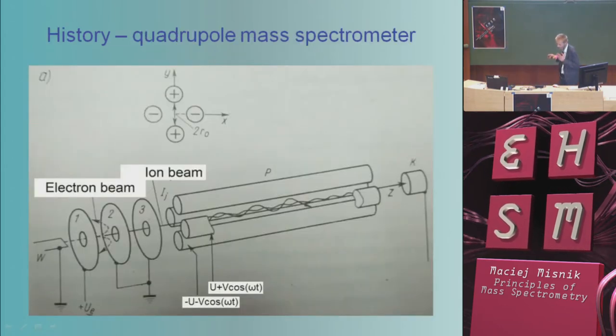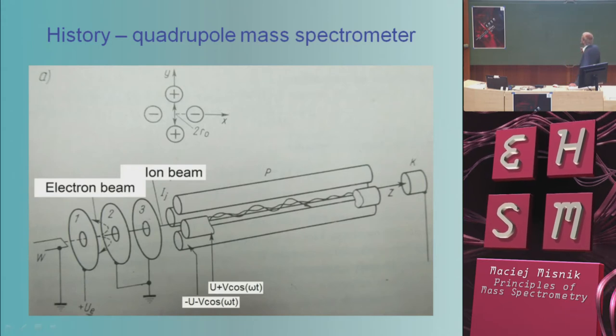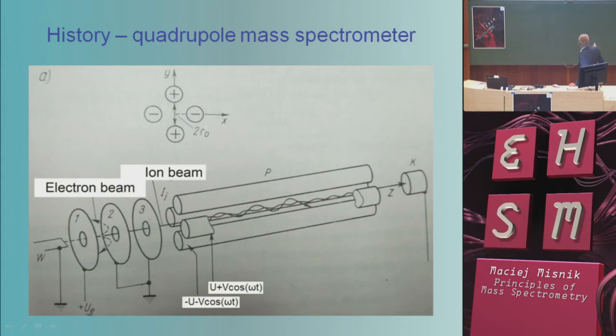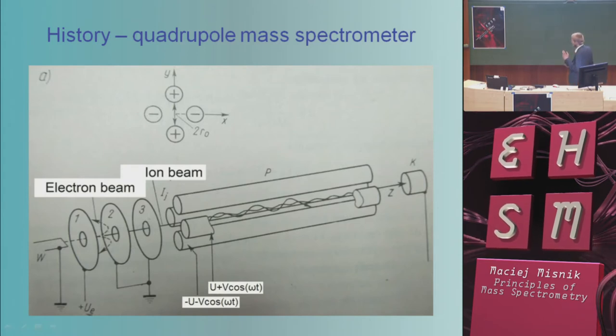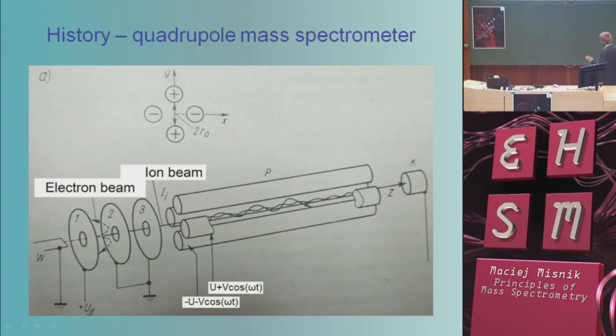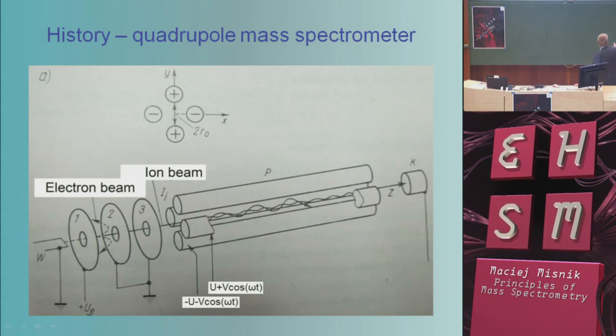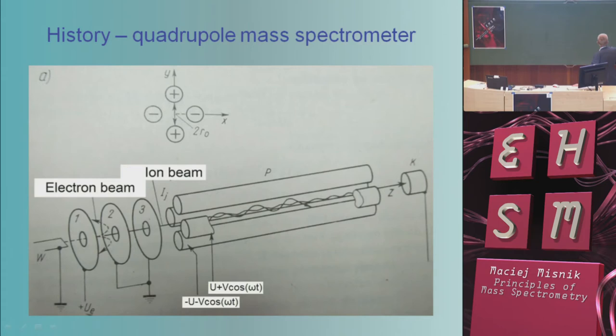Very popular today is the quadrupole mass spectrometer, constructed in 1953. It is built from four rods connected in pairs. On each pair of rods we apply a high-frequency voltage with a DC component, and ions oscillate between the rods toward the collector. Only ions with the correct mass-to-charge ratio can pass through the selector. We scan by changing this voltage, but the ratio of amplitude to DC must remain constant during the scan.